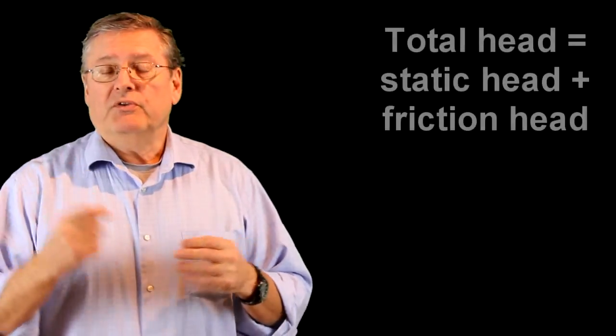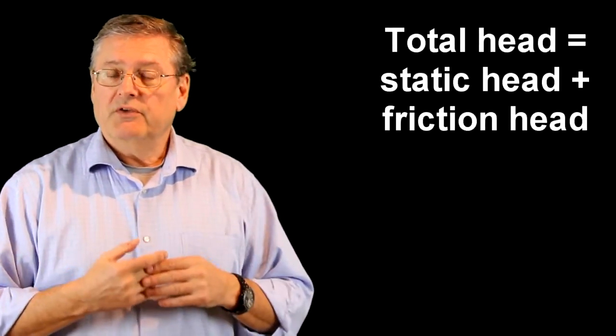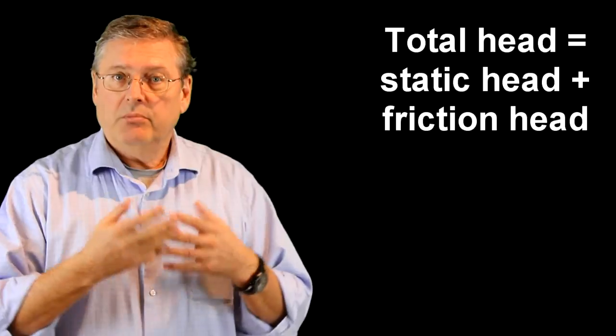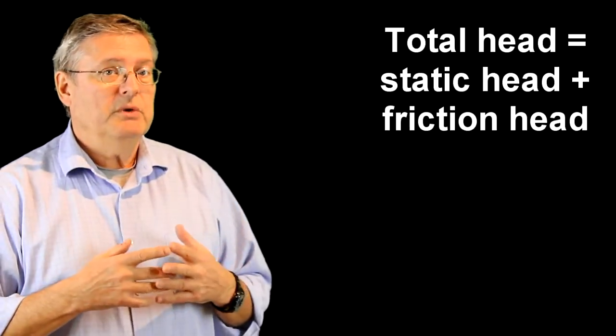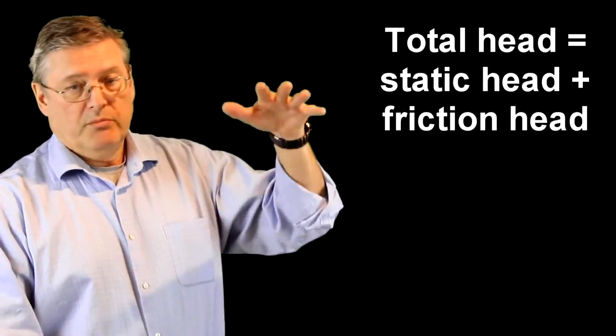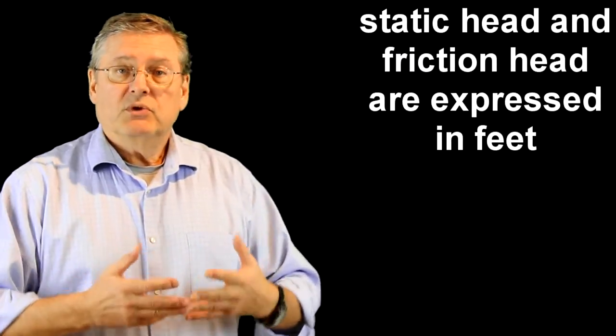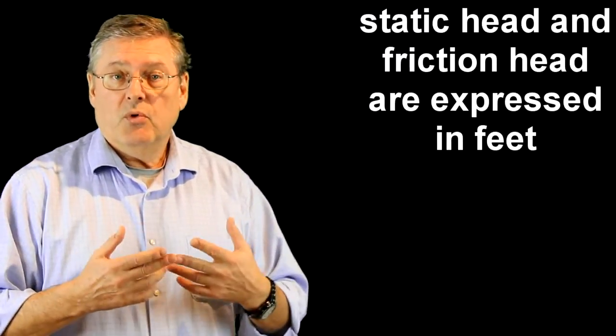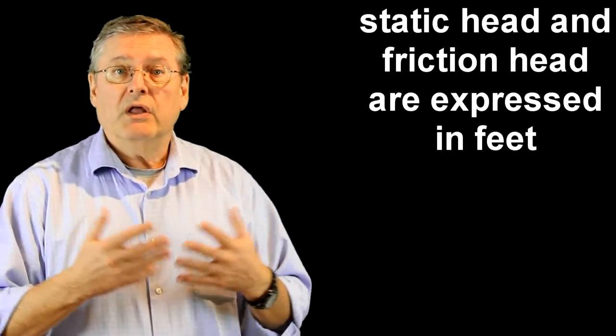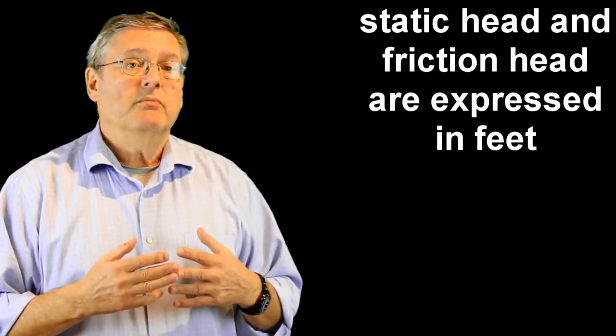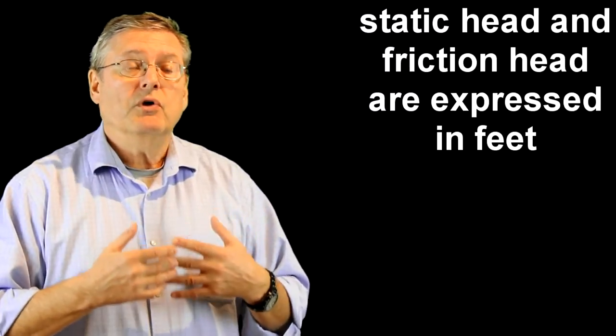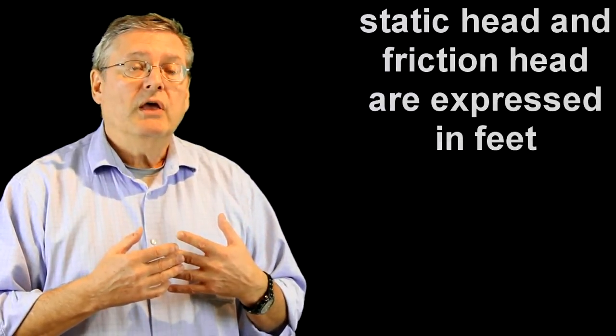Why do manufacturers use head as the main characteristic of their pump? Well there's two reasons. One is that head or total head is made up of the static head plus friction head. Static head is very easy to measure. You've got the field, you can measure surface levels of tanks and what have you. Friction head is easily calculated in terms of feet. And on top of it, static head is often the most important or significant component of total head, so it's very easy for everyone to use head as a characteristic.